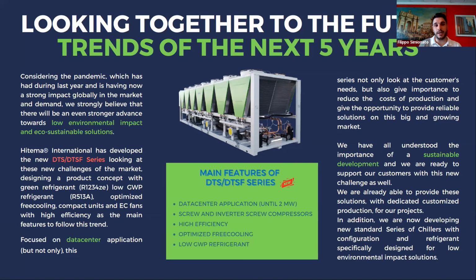The DTS is an air-cooled solution. DTSF is a free cooling solution. Of course, all these series follow the trend of the next 5 years. In fact, we can meet the challenges of the market using new olefin refrigerants like R1234ze or YF, but also low GWP refrigerants that the market allows us to use, like R513A or R515B. Of course, this series was born with screw or inverter screw compressors, but in the modular and back-to-back configuration, we can also move to turbo-core or scroll compressors.